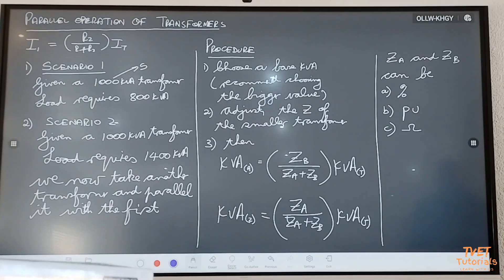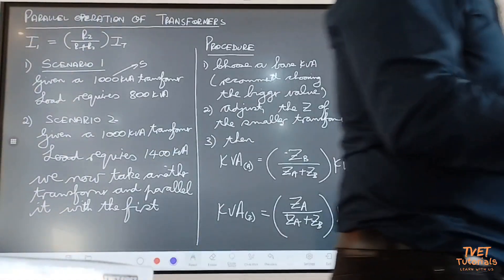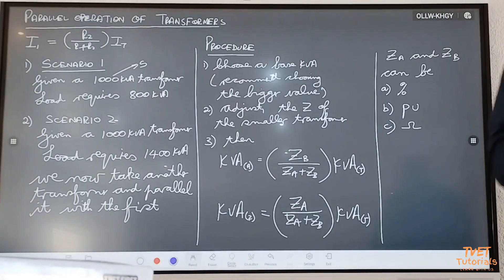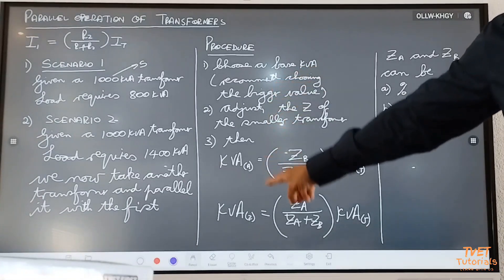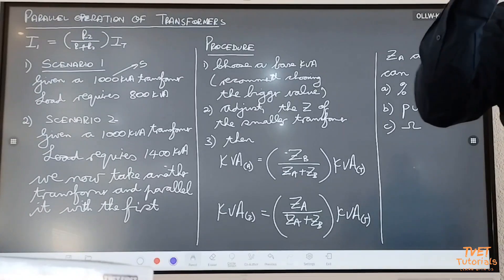Second important point: when both transformers have the same kVA rating, use the impedance as given. When the two transformers have different kVA ratings, choose a base kVA. One transformer was 1,000, the other was 500 — which one did I choose? The bigger one. Is that a rule? No — you decide. I recommend choosing the bigger value, but it doesn't matter.